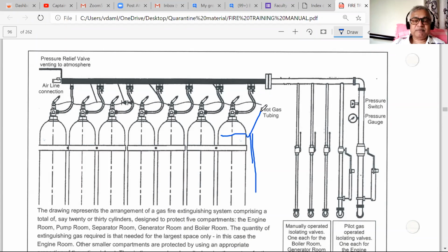That is level gauge checking. It's approved. Another one is actually weighing the cylinders. Now the problem comes. How will you actually weigh the cylinders? Are you going to remove 200 and take them somewhere? No. We generally have an arrangement on top. There is a bar there.